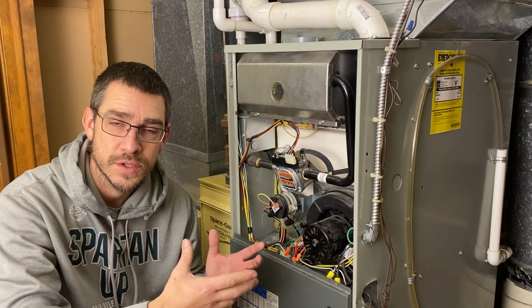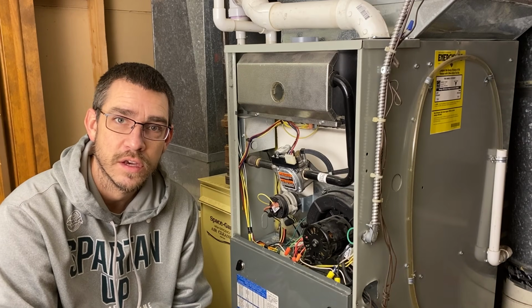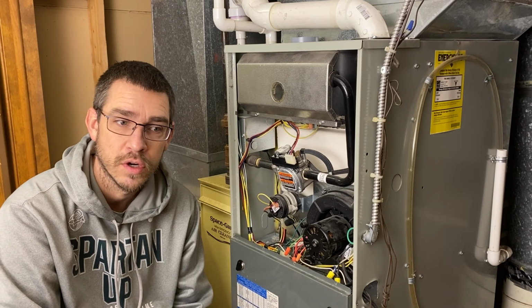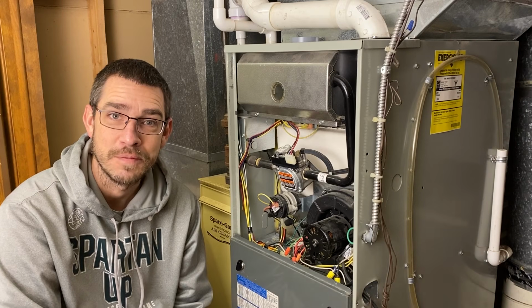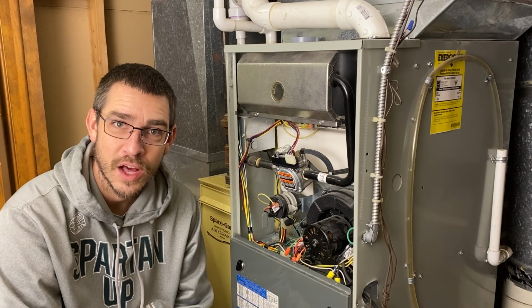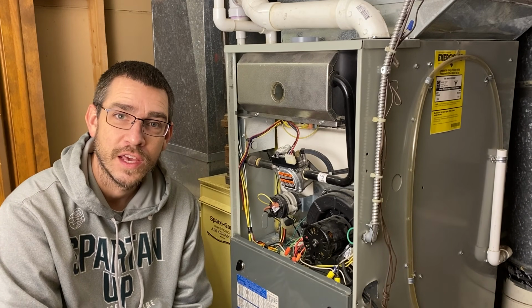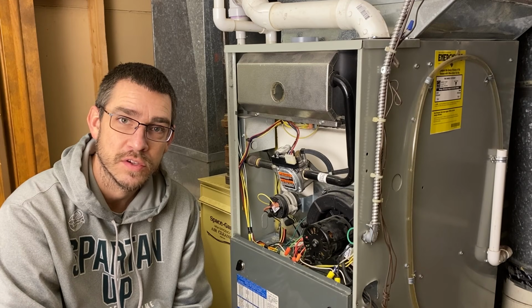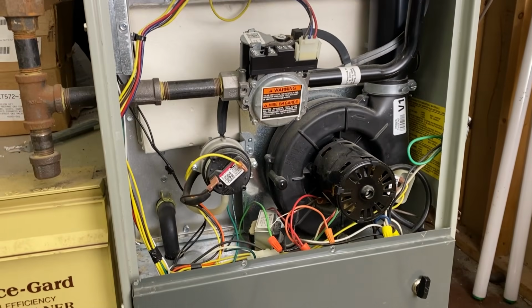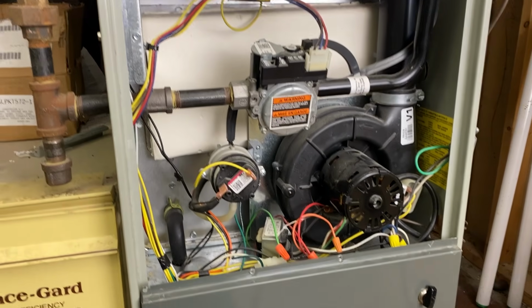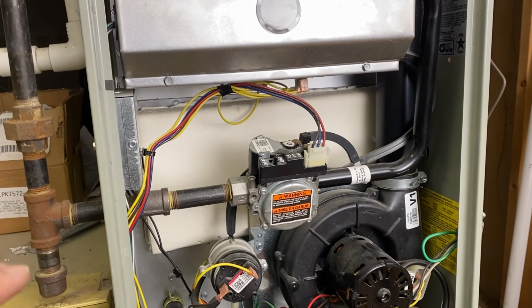There are a few sensors in here that can generally go bad and cause your furnace to not light, so you're not going to have any heat. If your furnace isn't working, this might help you identify the problem, order the parts and get it fixed yourself. Save yourself a lot of money. Okay, so I've got an older Trane furnace here. I'm not sure exactly what year it is, but this is what we use as our example.